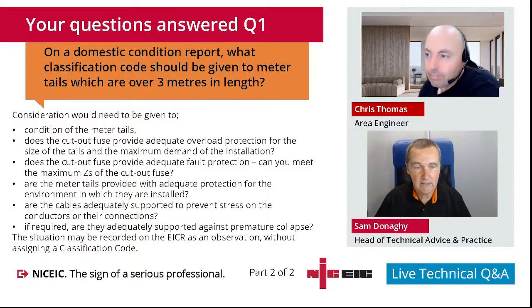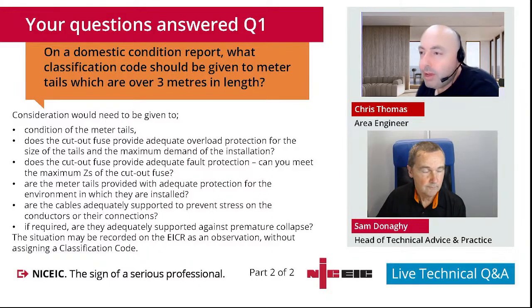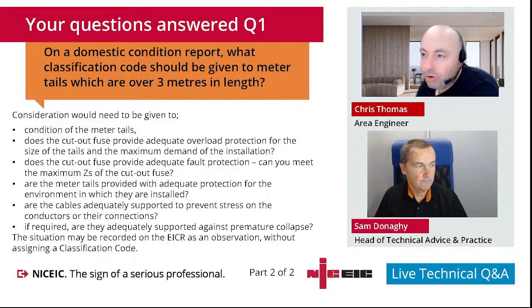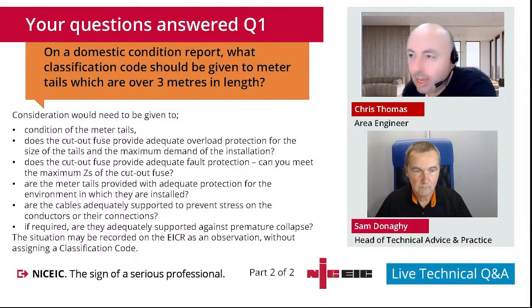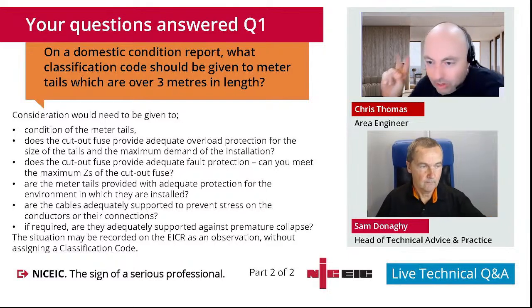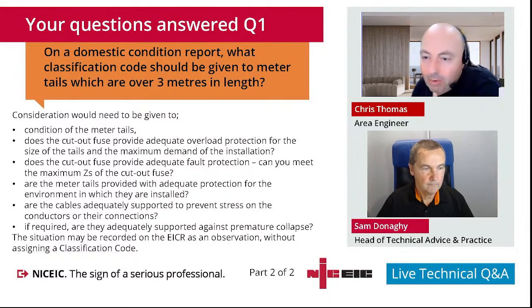So yeah. Would you add anything to that, Chris? No, pretty much summed it up well there, Sam. It doesn't necessarily rule it out as being unsafe or anything. I think a lot of installation electricians get quite obsessed with what I would refer to as the 3 metre rule. But as long as it's in good condition, it's being checked for being suitable for the installation, adequately protected, it's not automatically worthy of coding.